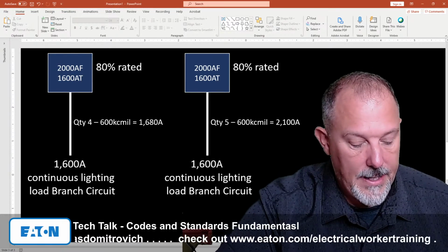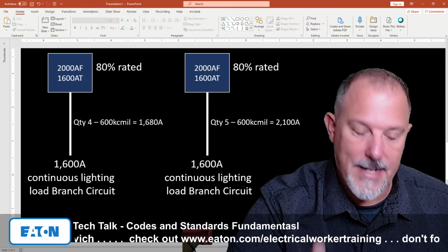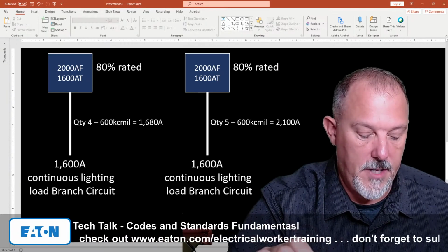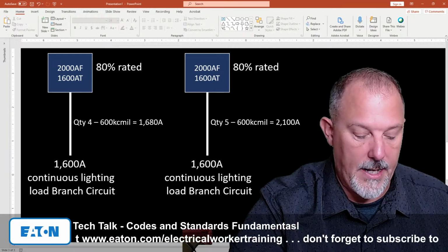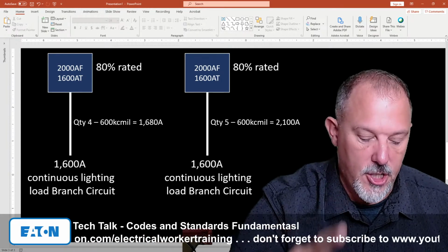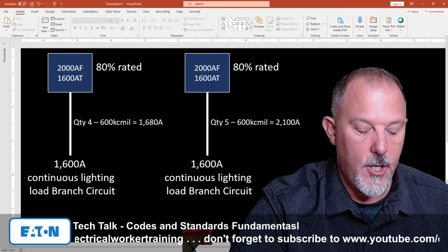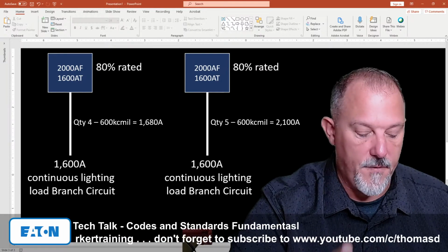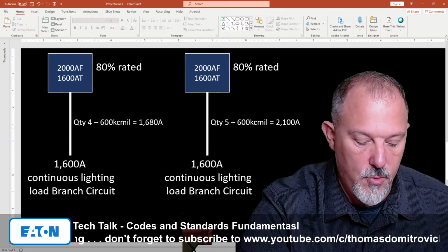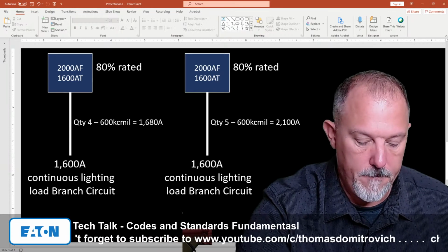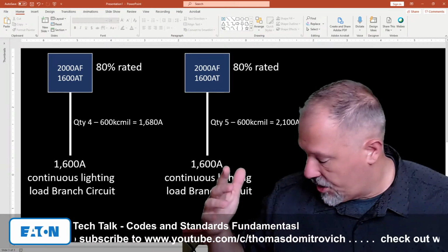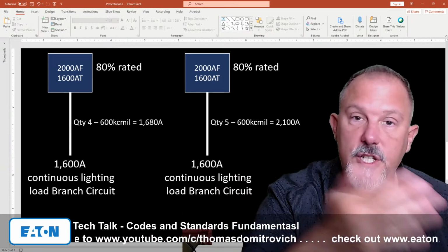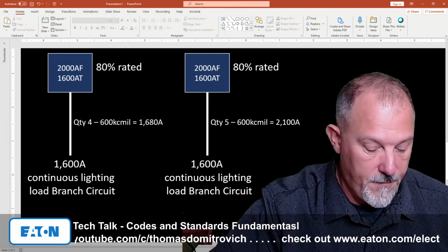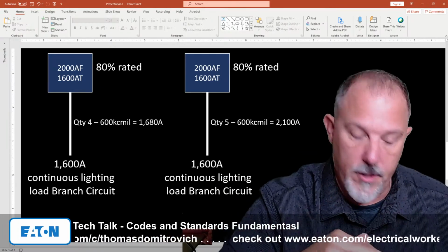240.6(C) says a circuit breaker that has restricted access to the adjusting means shall be permitted to have an ampere rating that is equal to the adjusted current setting. Restricted access shall be achieved by one of the following methods. I can locate it behind a removable or sealable cover, which on my breakers is that little door over top of the trip unit.